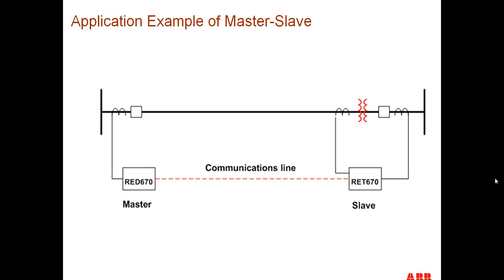What are the current limitations of the use of differential protection as a principal protection? The only limitation on a current differential relay is the channel. As long as you have a secure communications channel, you can use a current differential relay for that application. There are no limitations as far as series compensated lines, parallel lines, or very short or very long lines. There are limitations on how you use a distance relay on such lines because of voltage drops, and limitations on using distance relays with series compensated lines because of possible voltage inversions. But there are no such limitations when you use a current differential relay for those kinds of applications.